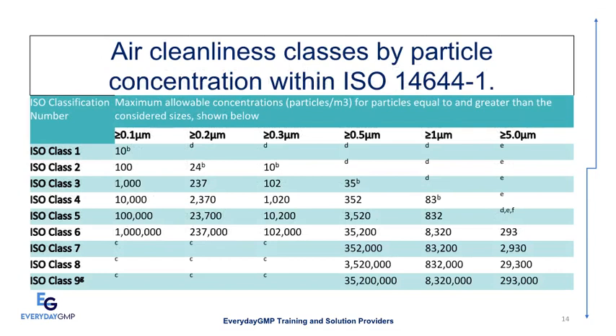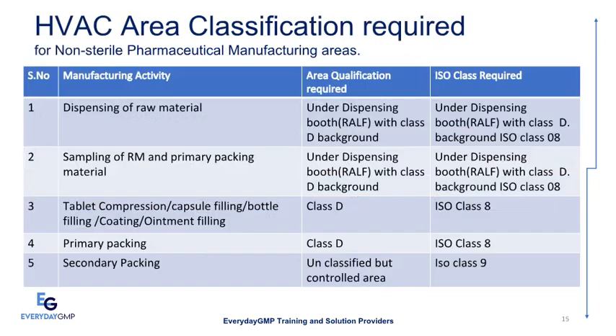Air cleanliness classes by particle concentration within ISO 14644-1, focusing on ISO Class 8. HVAC area classification required for non-sterile pharmaceutical manufacturing areas: dispensing of raw materials is under a dispensing booth with Class D background, equivalent to ISO Class 8. Sampling of raw materials and primary packing — including tablet compression, capsule filling, bottle filling, coating, and ointment filling — is in Class D (ISO Class 8). Primary packing is also in Class D. Secondary packing is an unclassified but controlled area.